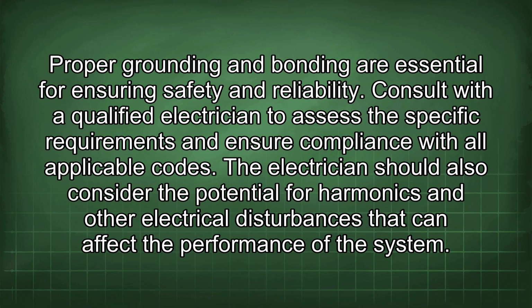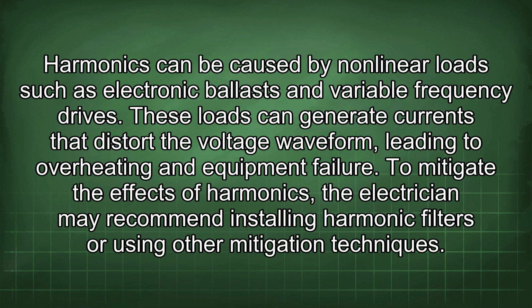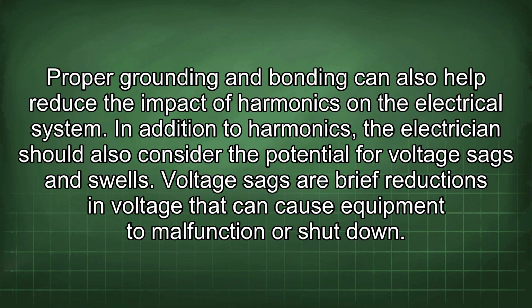The electrician should also consider the potential for harmonics and other electrical disturbances that can affect the performance of the system. Harmonics can be caused by nonlinear loads such as electronic ballasts and variable frequency drives. These loads can generate currents that distort the voltage waveform, leading to overheating and equipment failure. To mitigate the effects of harmonics, the electrician may recommend installing harmonic filters or using other mitigation techniques. Proper grounding and bonding can also help reduce the impact of harmonics on the electrical system.